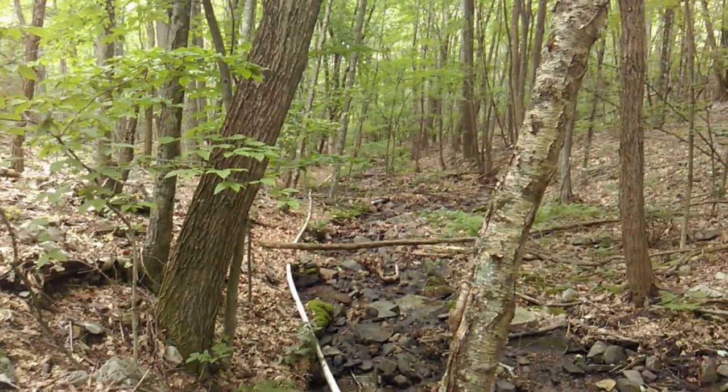It seemed like you had some wildlife issues too. I did have some wildlife issues on one of the soft joints. One of these pieces of radiator hose — I found one that was just squirting water, and I went up and there were just giant teeth marks in it. A bear or something like that decided to chew on it, either because it was irritating them or attracting them or whatever.